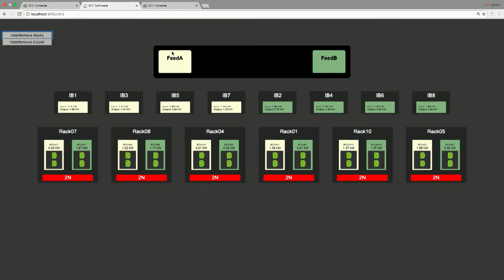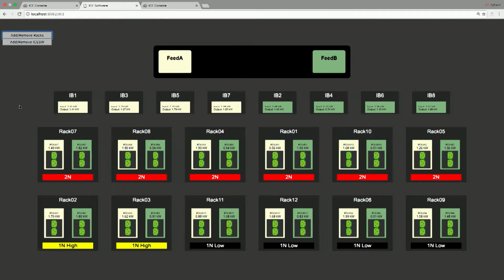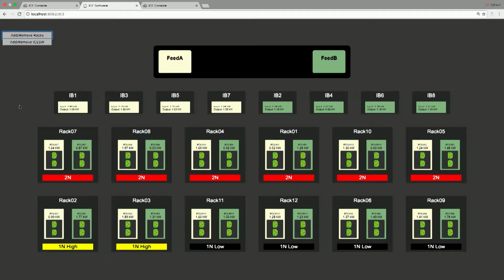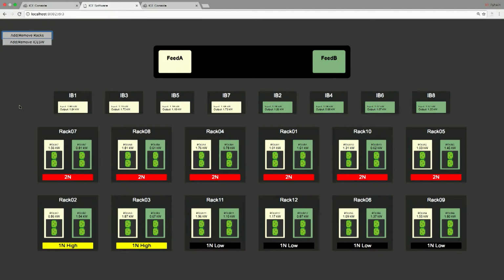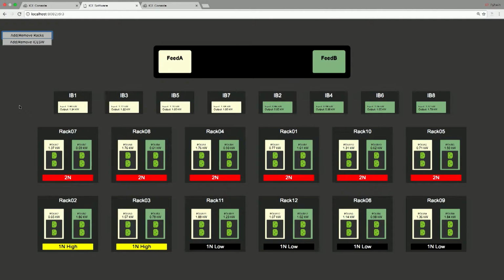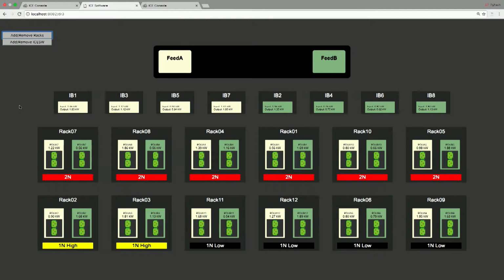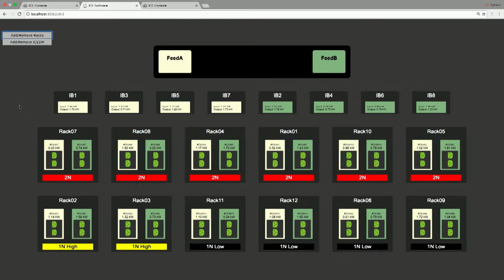The issue here is that you have 36 kW reserved for redundancy. You can't actively tap into it because you need it for redundancy purposes in case of a power interruption. You can imagine that if you wanted to tap into this redundancy and add 6 more racks, you would highly jeopardize the uptime of the facility in case of a power failure — you're overloading the circuit and can't control those additional racks.